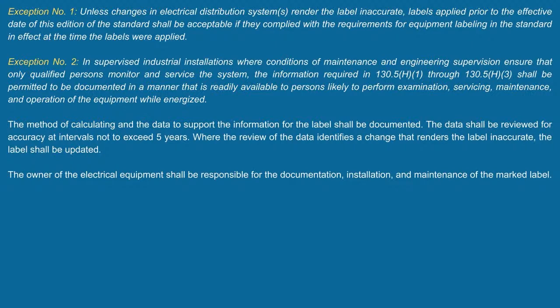Now, exception 2 gets into supervised industrial installations. And of course, when you're in a supervised location, this is where you have conditions of maintenance and engineering supervision that ensure that only qualified persons monitor and service the system. Now, when that happens, all of that information is required at this, or let me put it, shall be permitted to be documented in a manner that is readily available to who?